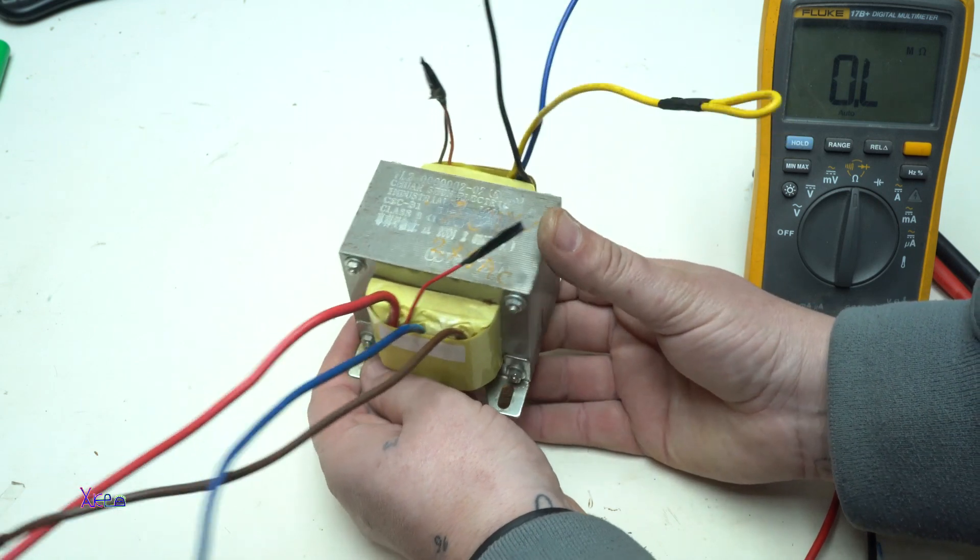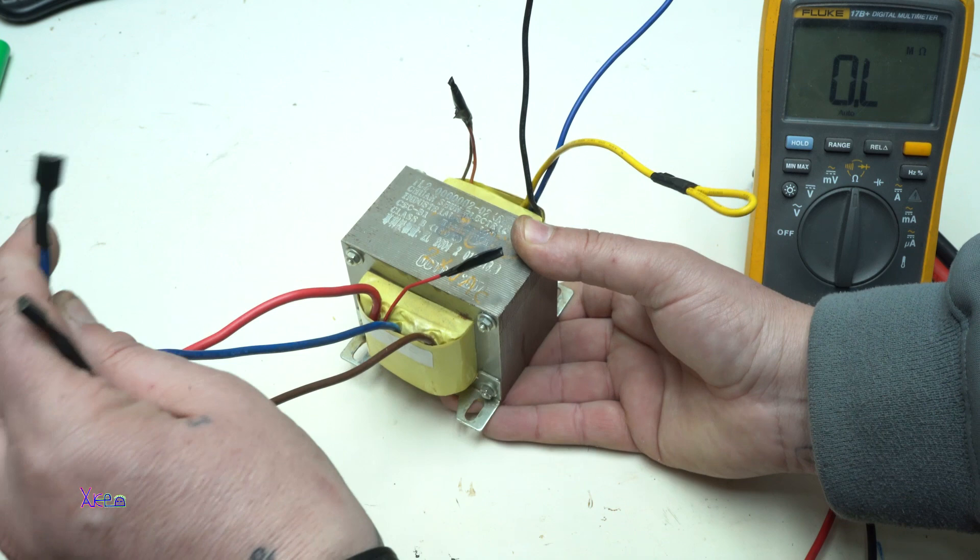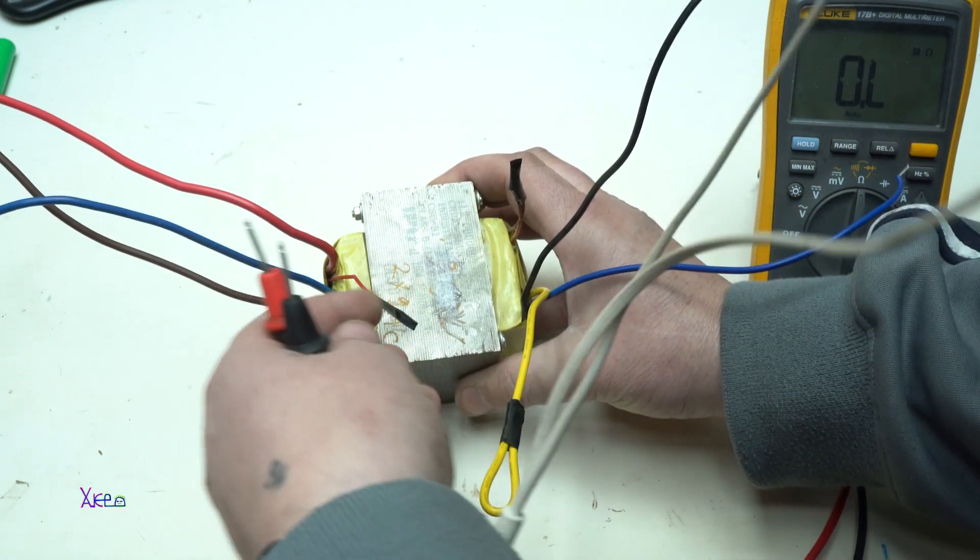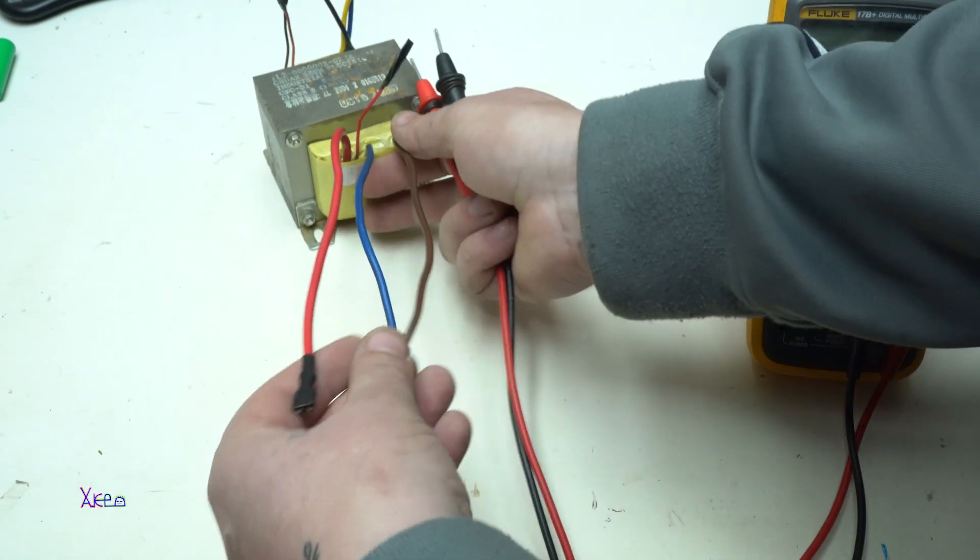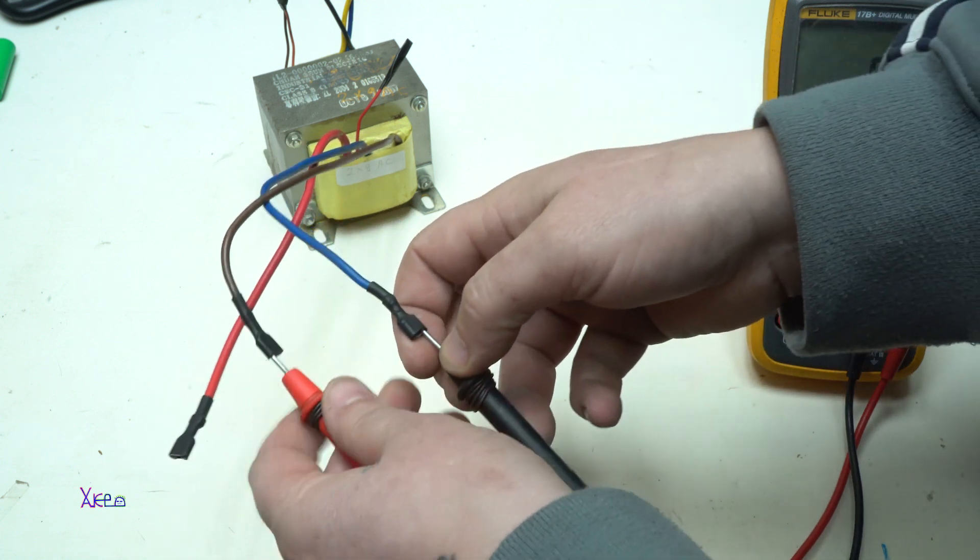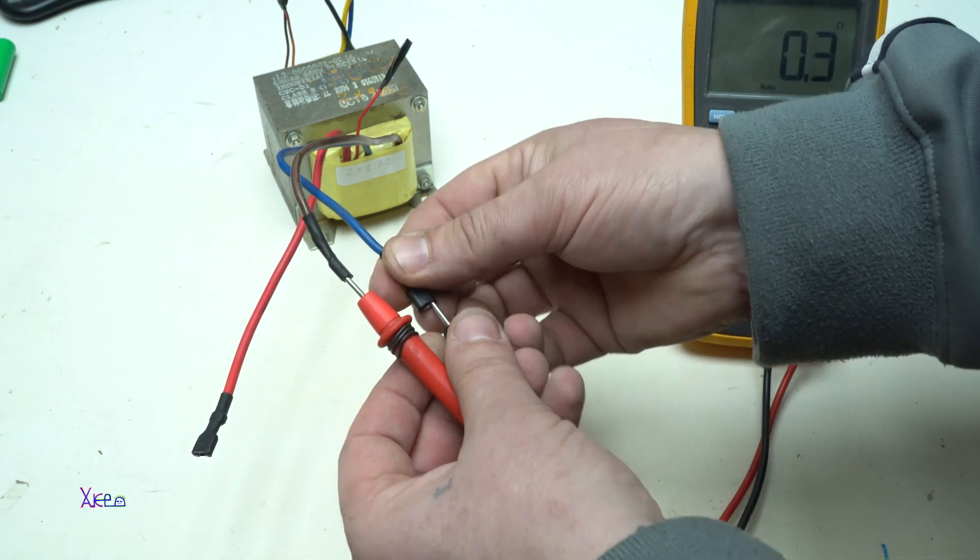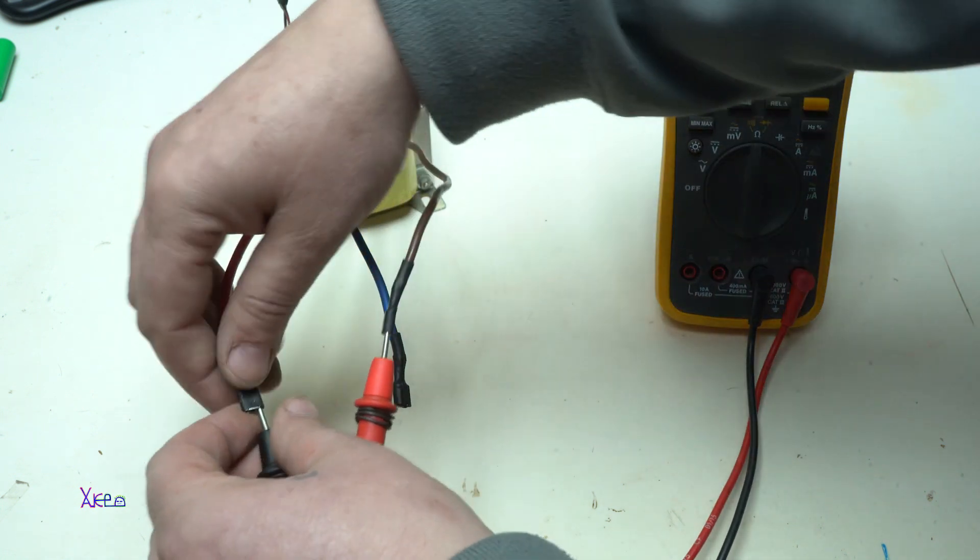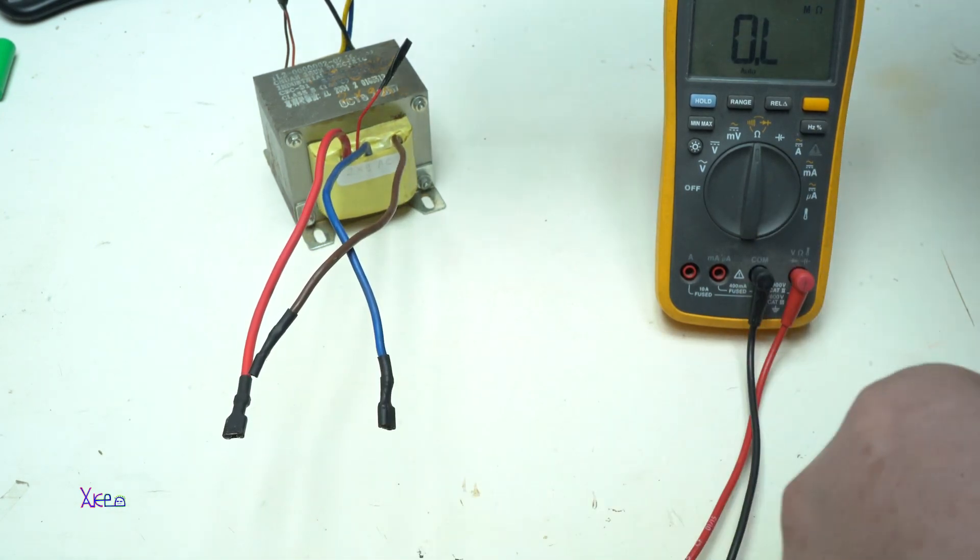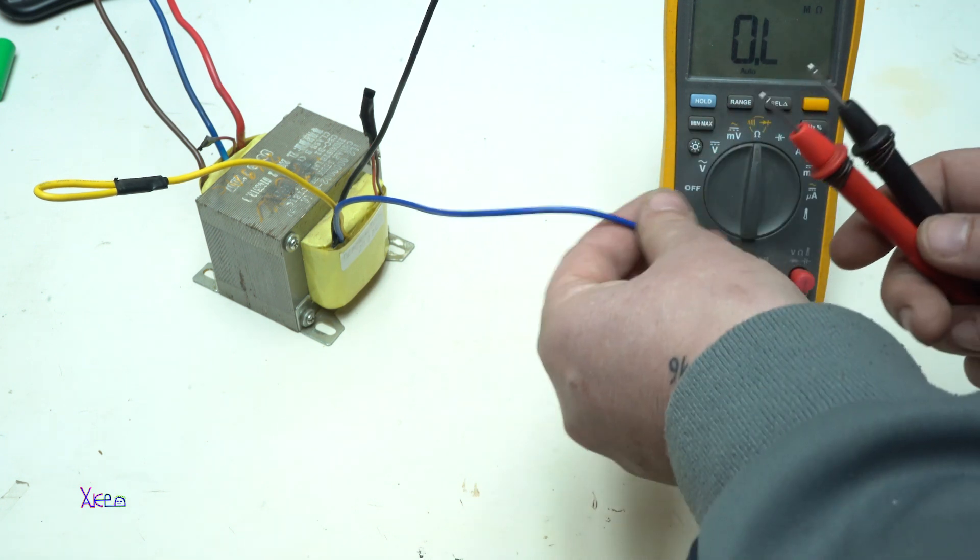This transformer have an input and output. It have a primary and secondary coil but you don't know which wires to use. For example you can see that wires are coming out from one side and other side. First we are going to measure the wires from this side. For example these two wires, blue and brown, and here we have 0.3 ohms. Let's measure brown and red at 0.4 ohms. And by the readings on the multimeter I can see that this is output. The input or primary coil should give much more resistance.